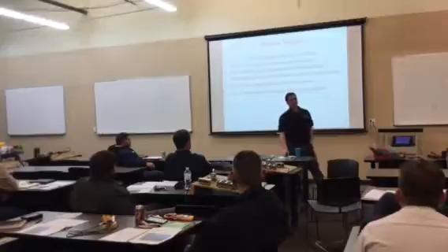Yes, sir. On like a 480 volt, what kind of gauge wire would you expect? Depending on how much current the device is going to consume. It's another kind of potentially misleading thing about high voltage circuits: they typically have smaller diameter conductors than low voltage circuits do, because they're going to carry less amps to do the same amount of work, or what we covered before lunch.